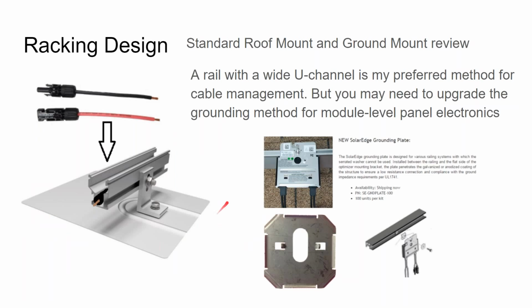This is a wiring technique I came up with for the Solar Edge system. When picking out solar racking, I really like to find a rack that has a U channel in the rail. Sometimes the rail is more like a solid bar, and you have to get little clips that hang off the side for your home run cables - I don't like that. I like the U channel because it becomes a raceway or cableway for your wires up on the rooftop, and if you can slide your solar cables into it, it also acts as a guard against squirrels and critters for maximum protection.